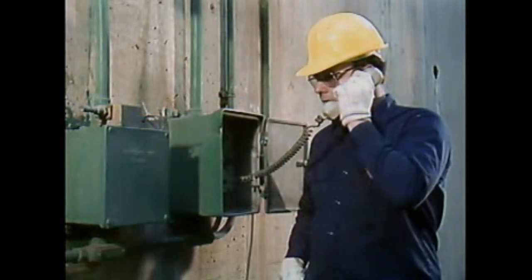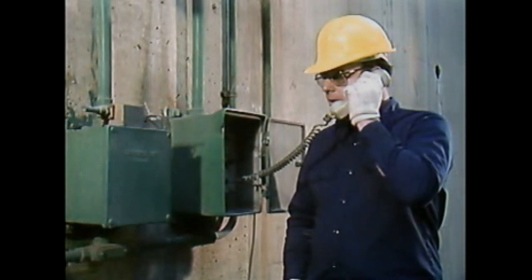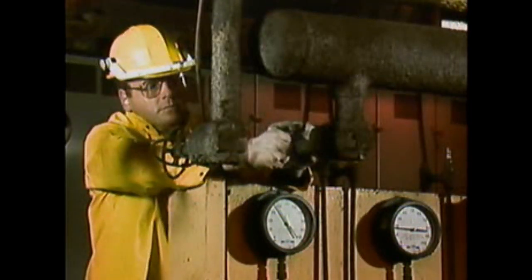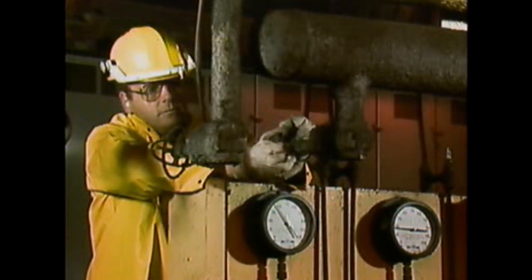Before a liquid system can be filled, the system must be prepared to keep the liquid from leaking out and to allow for air to be removed as the system is filled. To see how this is done, let's watch an operator fill a system. The operator has been notified that maintenance has been completed and the system is ready to be filled. One of the first things to do is make sure that all the drain valves are closed.